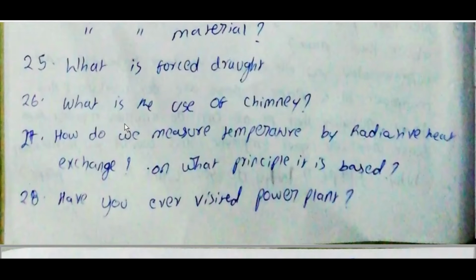There is a hot body from which radiative waves pass through a lens and get focused on a black body, which is the temperature detector. Then it is connected to a measuring instrument. Basic principle: it measures an object's temperature by sensing heat or radiation emitted from the object without making any contact with the object. Basic components: optical system and detectors.